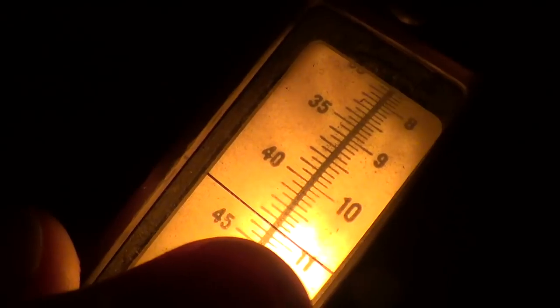Now let's use the strobe to measure the rotational speed of the drill. We stop its motion, and then we look down here at the low speed dial on the right. Let the camera adapt to the bright light, and it's a little less than 11. Times 100 means that the drill is rotating at a little less than 1100 RPM.